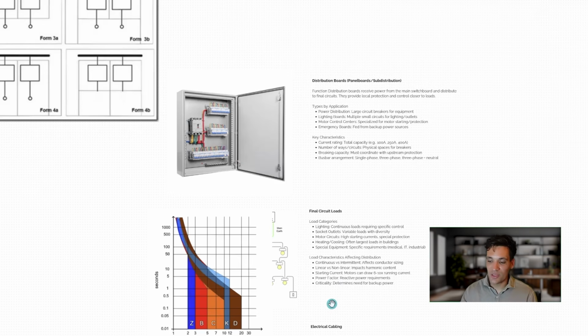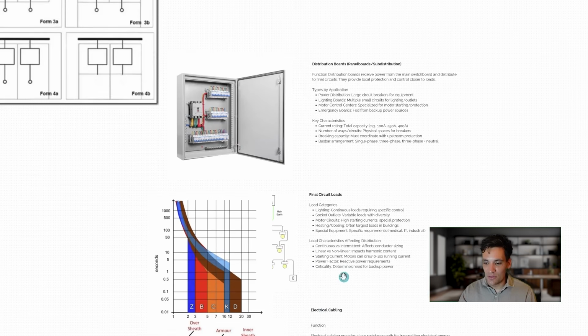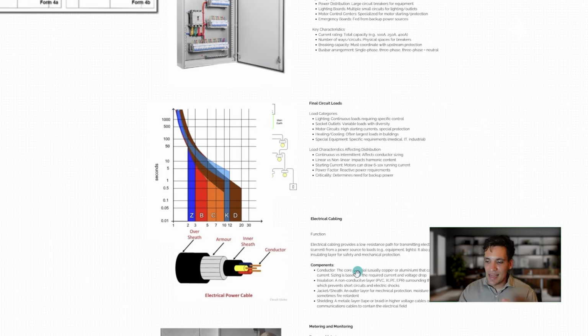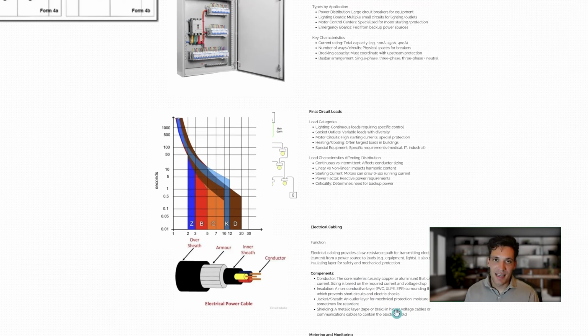We've also got to consider some loads might not have continuous power requirements. For example, a pump or a motor will draw a lot of power to start spinning, but once it's on, it needs less. Loads can have different power factors. You can have inductive loads that cause a lead or a lag. And it's important to understand these different load profiles to properly size the system, and it all comes back to demand factors. Everything in our facility is going to be connected by cabling.